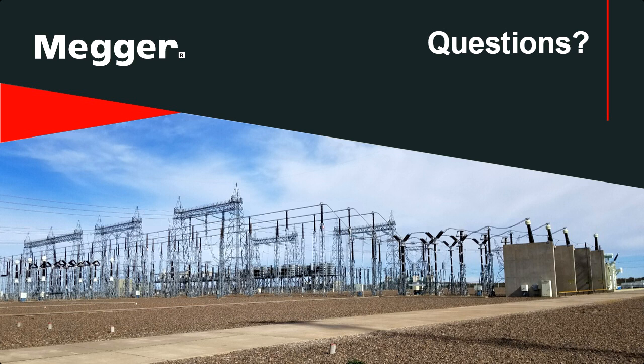So back to the question of the different breaker tests. So the standard range, so contact resistance, a lot of people call that DLRO or a ductor test, right? So all you're doing is contact resistance, and depending on the standard of IEEE or IEC, you're going to use either 100 amps for contact resistance for IEEE or 50 amps for IEC. And that's just going to give you a low ohm value, usually in the micro ohms.